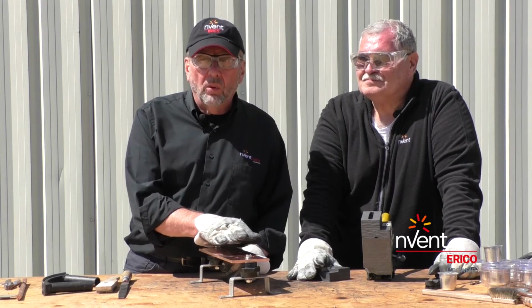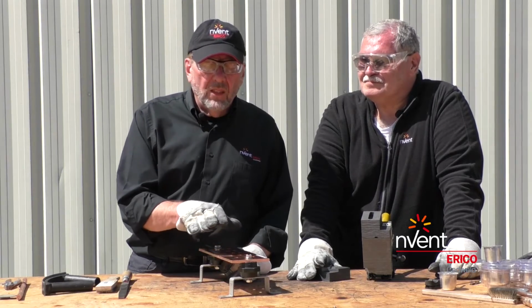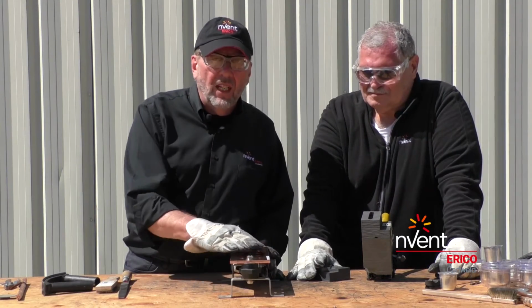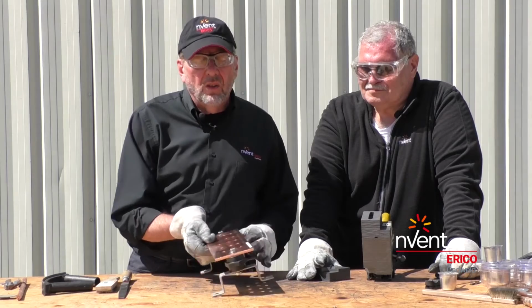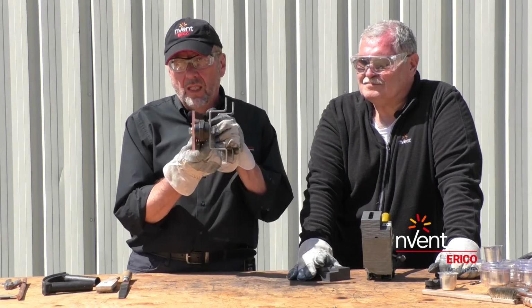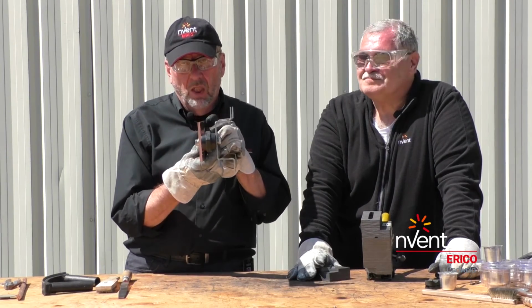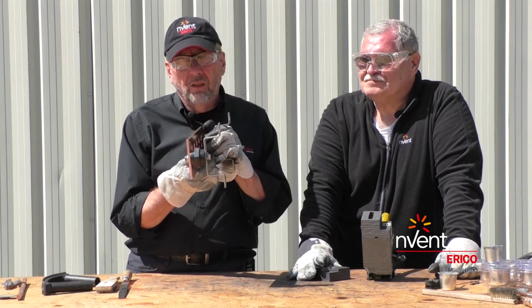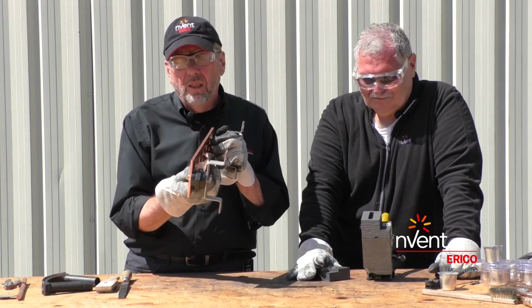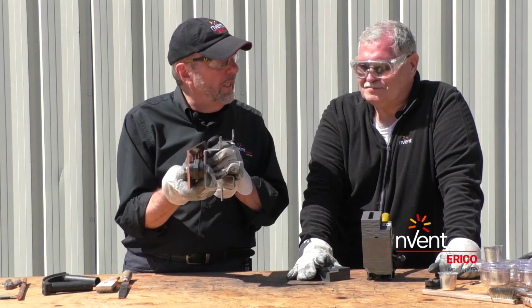Especially for grounding or earth bars, making the connection with the bar in this kind of position is much easier than trying to do it with the bar in situ, as engineers say, mounted on the wall. There's a lot of worry then about clearance and gravity trying to pull my welding material away from where we need it.